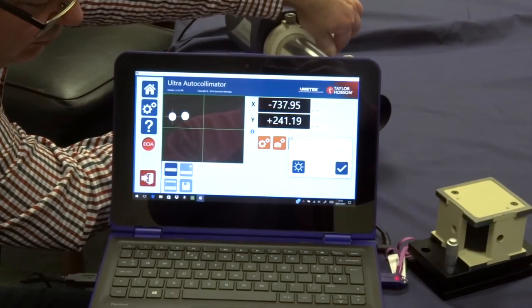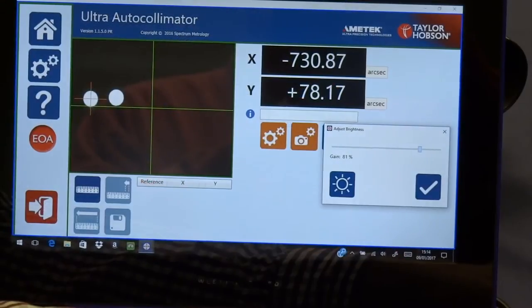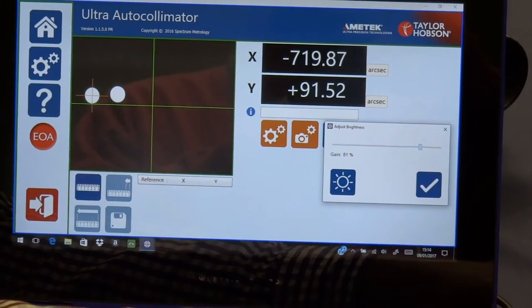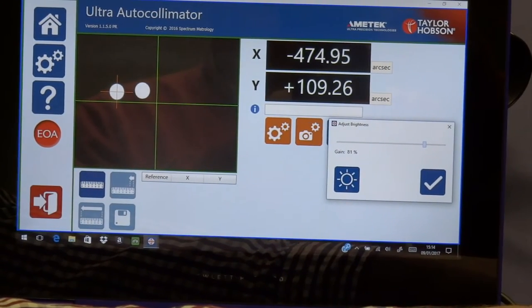We can take these visual images off the autocollimator screen by simply twisting the optical square. Remember, twisting the optical square does not affect the 90 degrees.